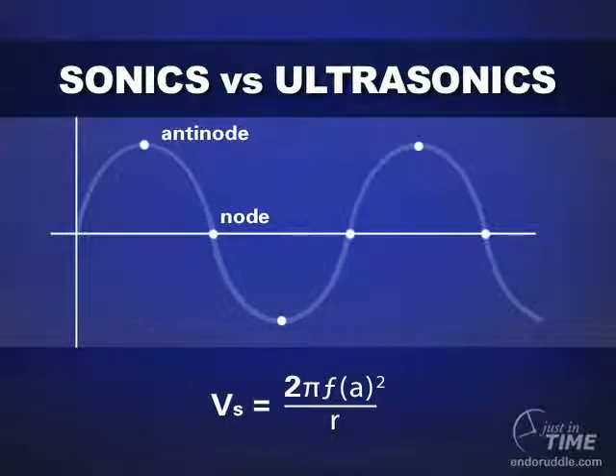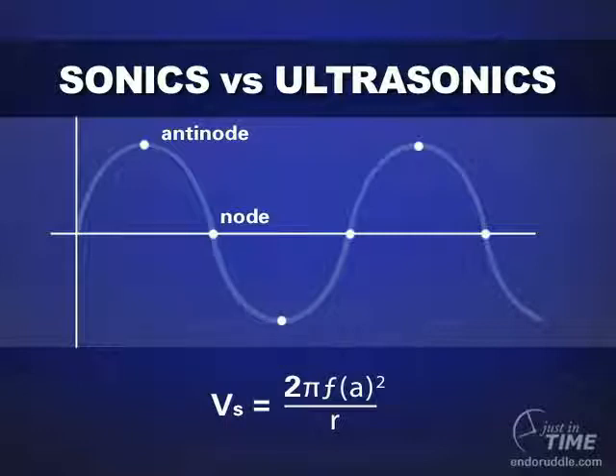Here you see the formula for streaming velocity — you might just think of streaming velocity as the potential to clean. Cleaning is directly proportional to the frequency, exponentially proportional to the amplitude, and inversely proportional to the radius of the instrument. Some groups in the world are looking at high frequencies like ultrasonics to solve the cleaning problem. Other groups are looking at amplitudes, because amplitudes that are squared have a big impact on cleaning potential.